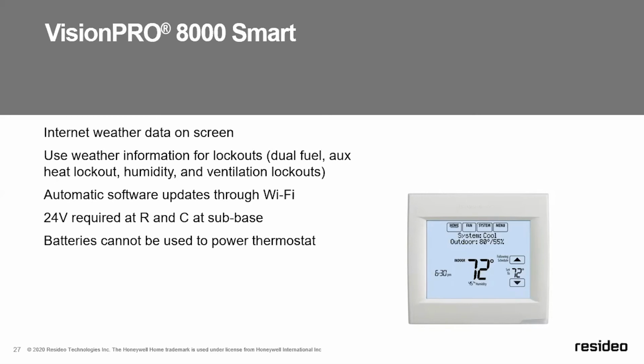The internet weather is provided on screen. It uses this weather information as the ability to control lockouts for dual fuel operation, auxiliary heat lockout, humidity, and ventilation lockouts. The 8000 Smart also will receive updates automatically through the internet if updates are sent. It does require 24 volts at the thermostat, so you need a minimum of 5 wires or more for your equipment, or 4 wires with a wire saver module. This does not offer any battery capability.